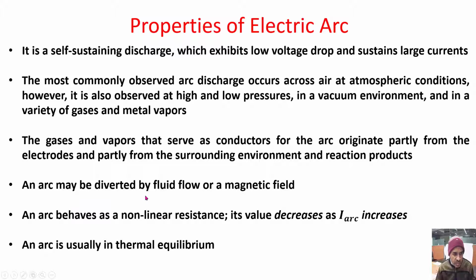An arc may be diverted by fluid flow or magnetic field. Because the arc consists of a current, it can be deflected by a magnetic field, and since it physically consists of particles, fluid flow can also push the arc away. Therefore it may be diverted by these two things. An arc behaves as a nonlinear resistance. Its value decreases as the current of the arc increases, just as we have seen. An arc is usually in thermal equilibrium.